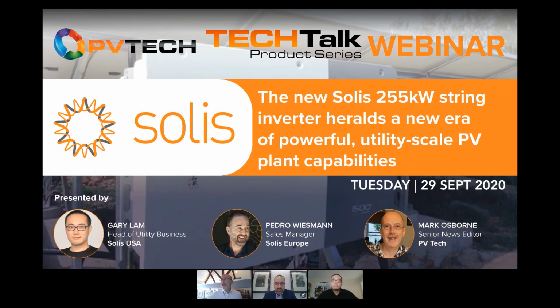Okay. Actually, just related to that, a quick one that's come in, and I'm looking at the time as well, so we've only got a little bit left. Can you confirm that your inverter can work at night, generating reactive power to the grid? Yes. This inverter does support nighttime VAR generation. It depends on region. So in Europe, likely this is open. In the US, it really depends because that's about the utility requirement. Yes, but this unit supports nighttime VAR generation.